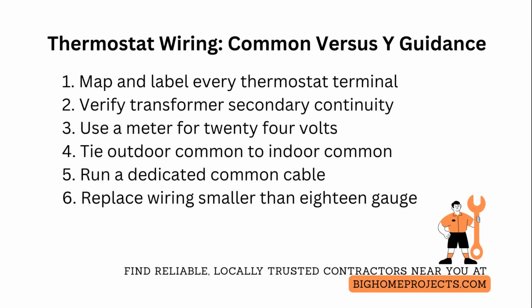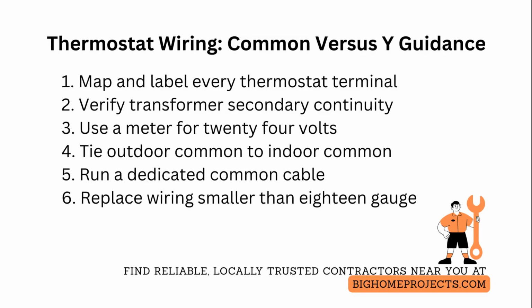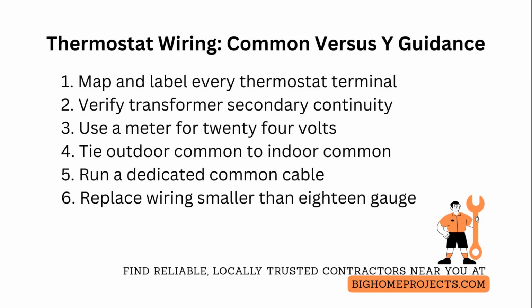Use a meter to check for 24 volts AC on call and common when the thermostat is calling, and never assume color coding is correct because installers reuse wires and swap colors. Document the voltages and note any shared neutrals or multi-transformer setups.